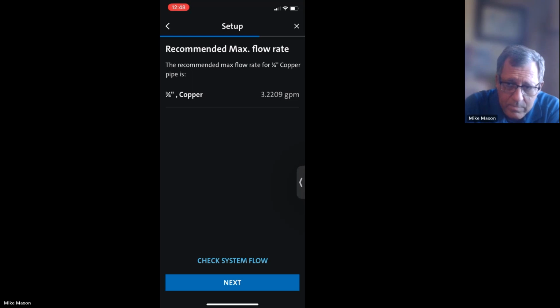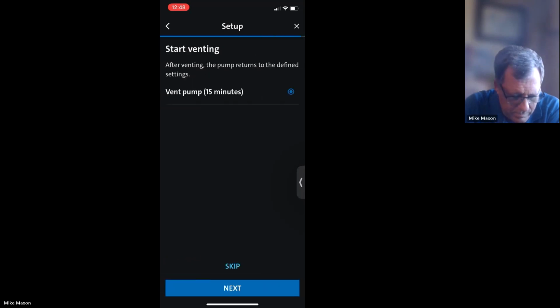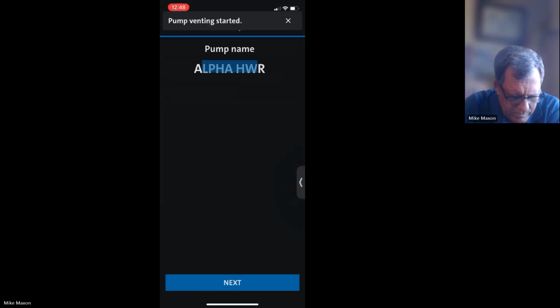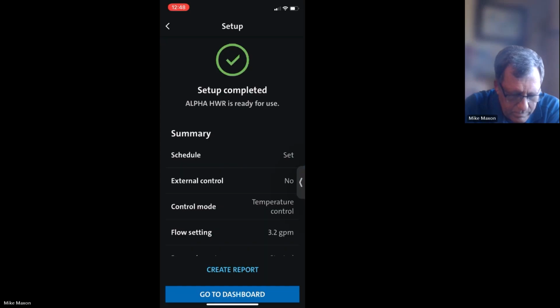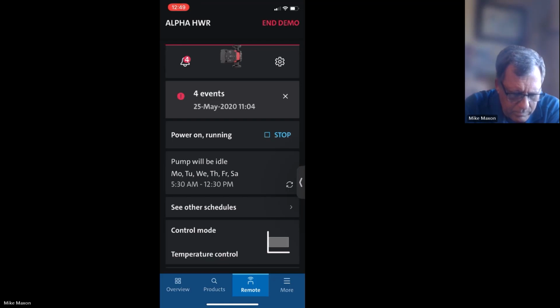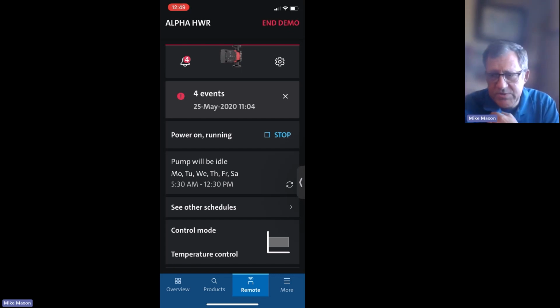And you were right about the PEX, because we also represent Uponor. So they're saying no more than 2 feet per second for return lines. And that's what you guys have done, you've restricted it so that it can't do more than 2 feet per second. And in all honesty, on a recirculation system, you shouldn't need that much flow to get the hot water. So in this demo that I did here, you saw I set it at 3/4 inch copper pipe, and the max flow there was, I think, 3.2. So I took that, and then you get to the dashboard.